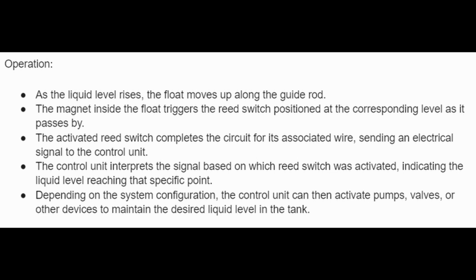The magnet inside the float triggers the reed switch positioned at the corresponding level as it passes by. The activated reed switch completes the circuit for its associated wire, sending an electrical signal to the control unit. The control unit interprets the signal based on which reed switch was activated, indicating the liquid level reaching that specific point. Depending on the system configuration, the control unit can then activate pumps, valves, or other devices to maintain the desired liquid level in the tank.